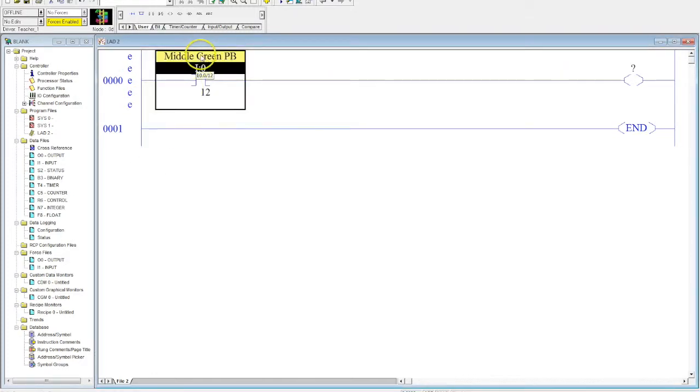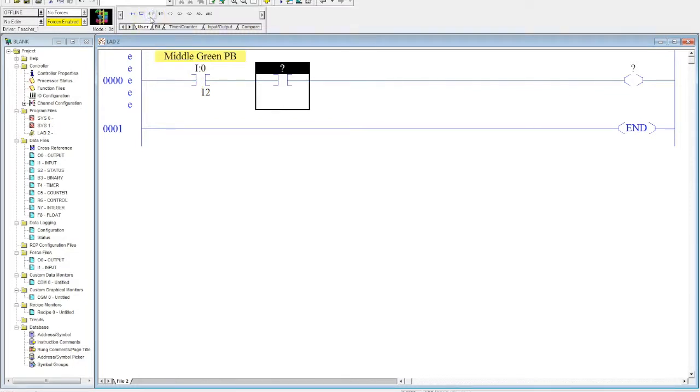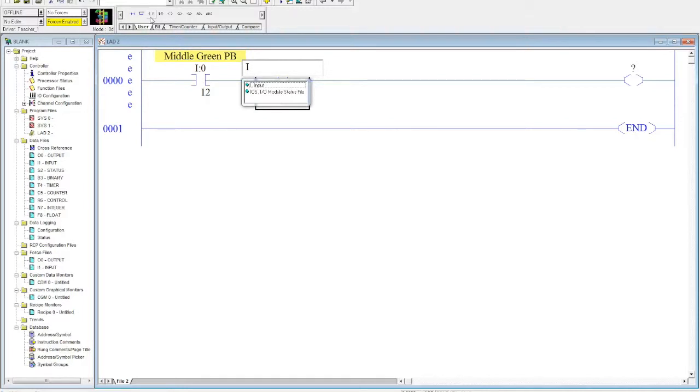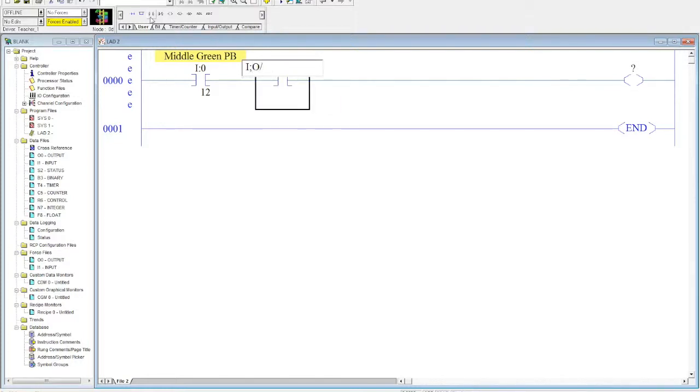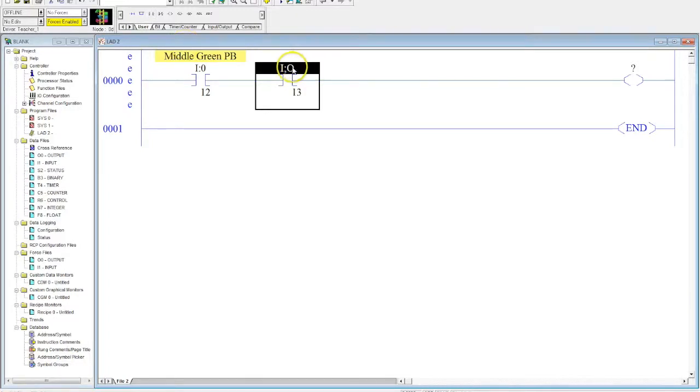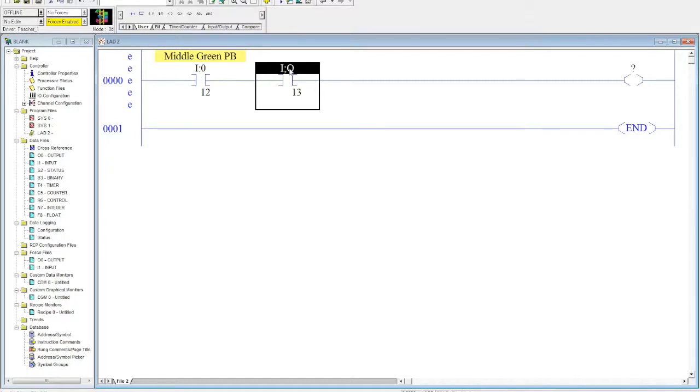Now let's go back to this idea of a semicolon and what the purpose of it is. Let's say I wanted to put another switch in here, and I do I, semicolon, but instead of hitting 0, I accidentally hit O. And then I do forward slash 13, the right green button, and I hit enter. Now look what happened there. One, the screen didn't pop up asking me to identify it with a name. Now you can actually go into files and set that up so that doesn't happen, so that's not a major concern if it doesn't appear. But the big one is, look, the semicolon didn't change to a colon. That immediately tells me that's where my problem is.